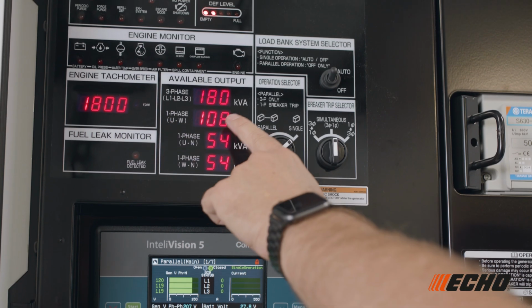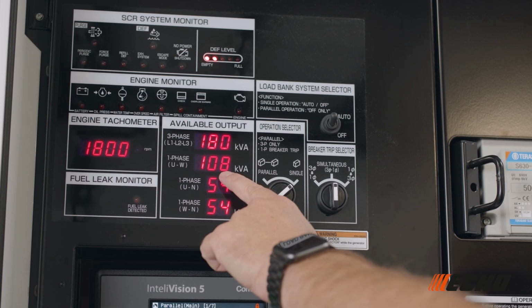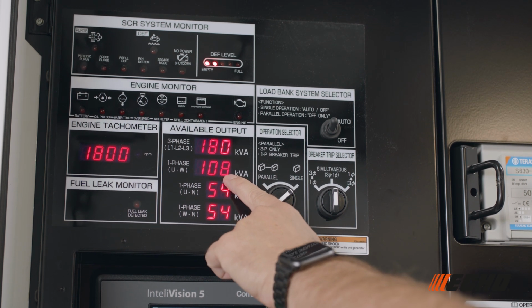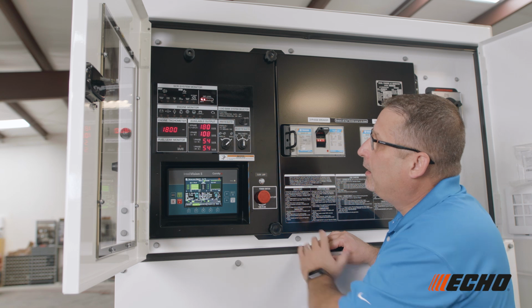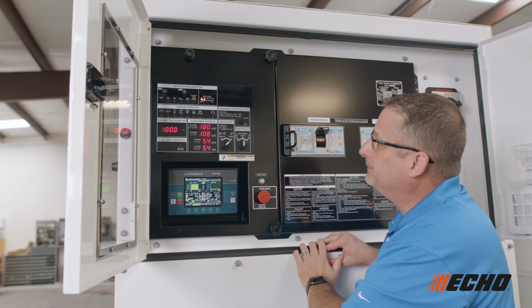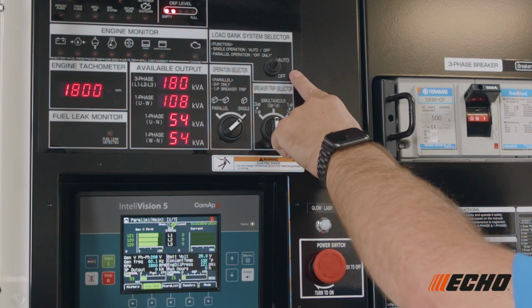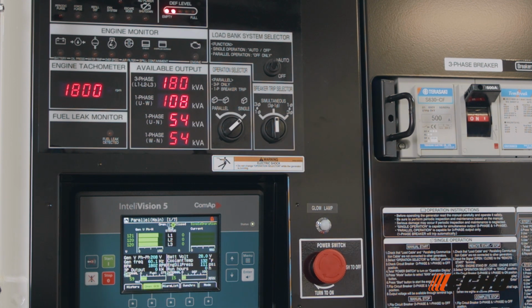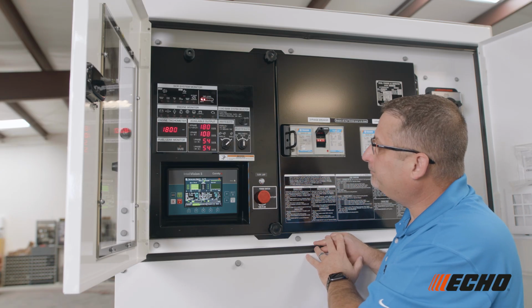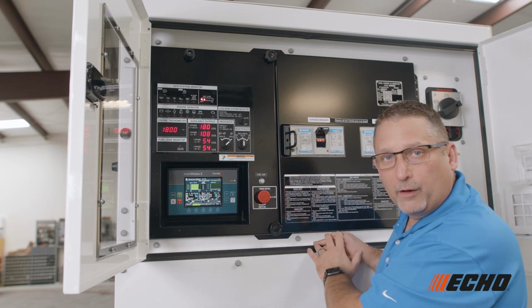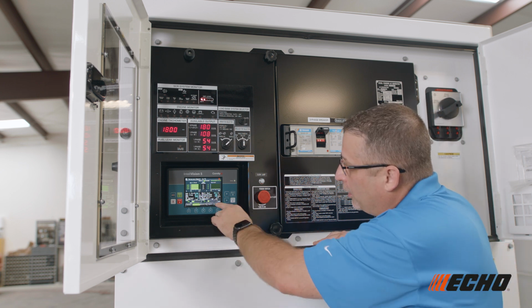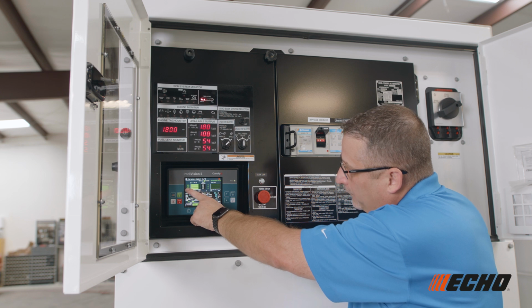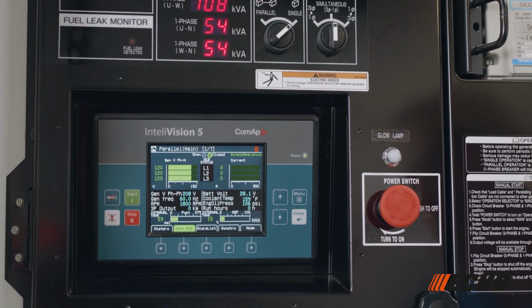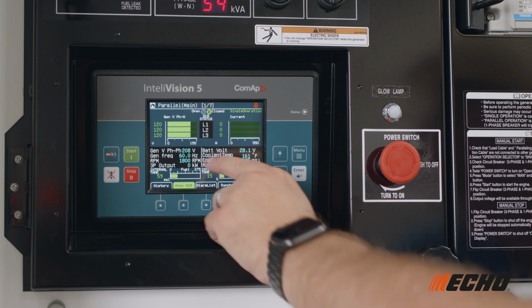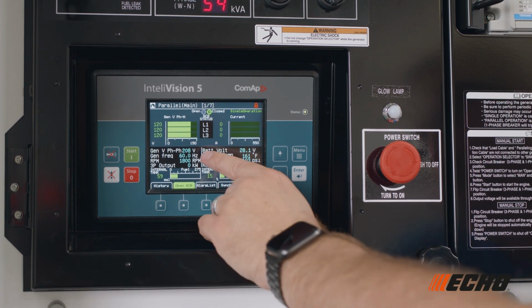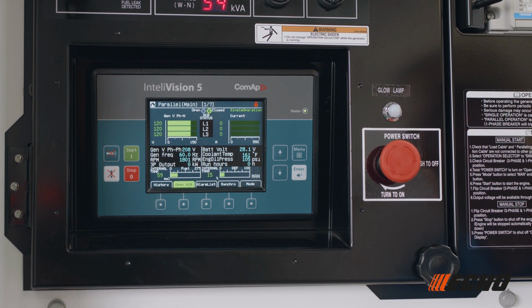You have 180 kVA of three-phase load available, 108 kVA of single-phase load available, or a combination thereof. You'll notice you're at 1800 RPMs. It's your load bank system. It needs to be in the auto position on single unit operation. Let's go through the controller features. You'll notice it had all of your readings. You'll see that you got leg to leg. You'll see that you have your voltage, which is at 208 volts, 60 hertz on your frequency, 1800 RPMs.